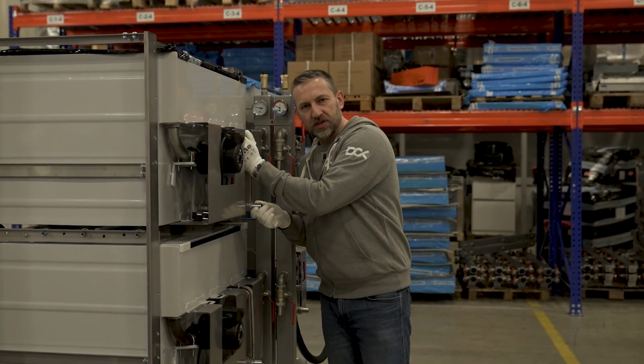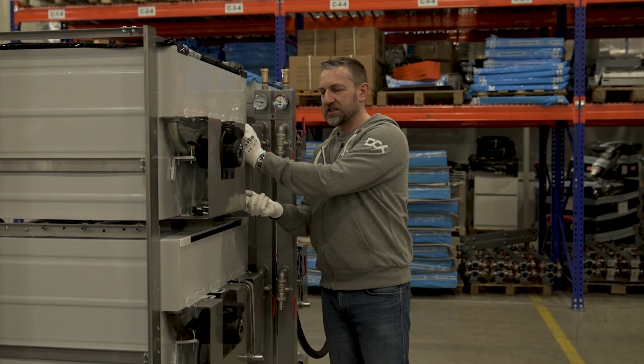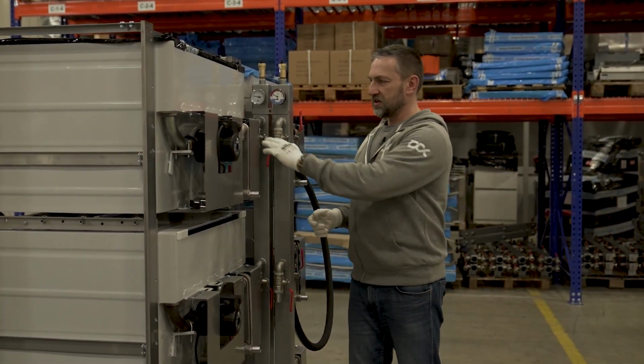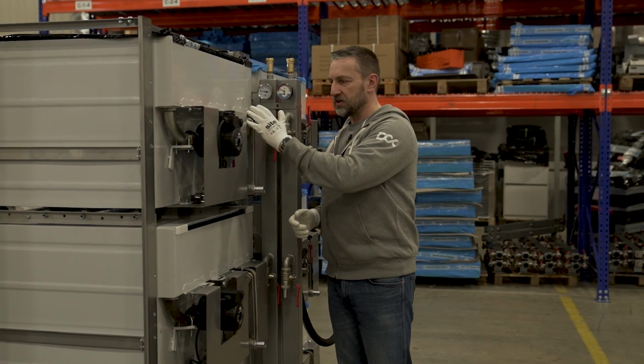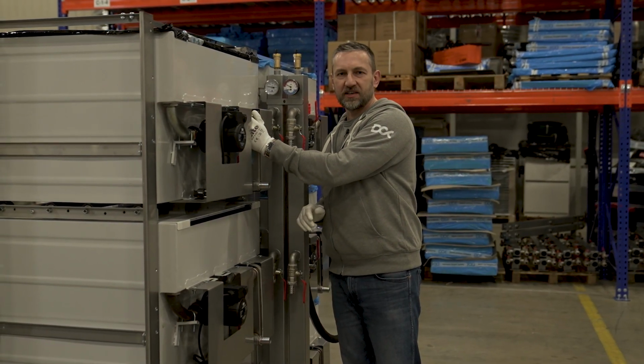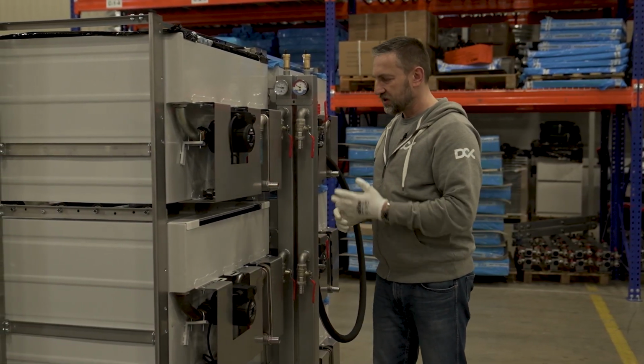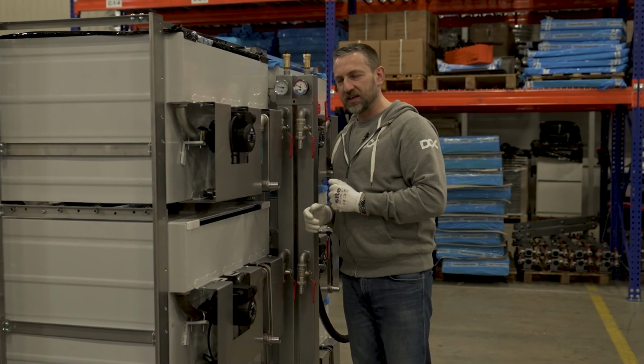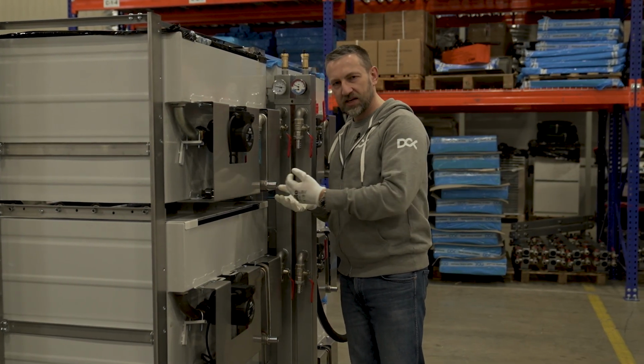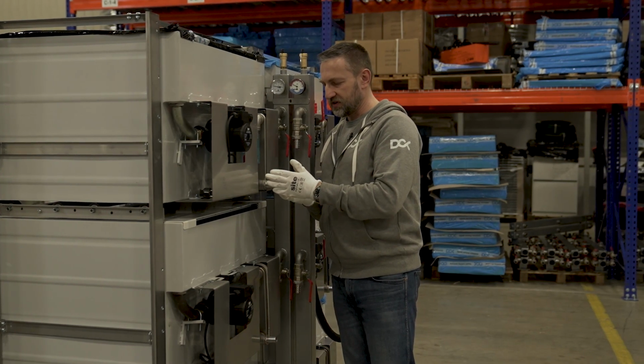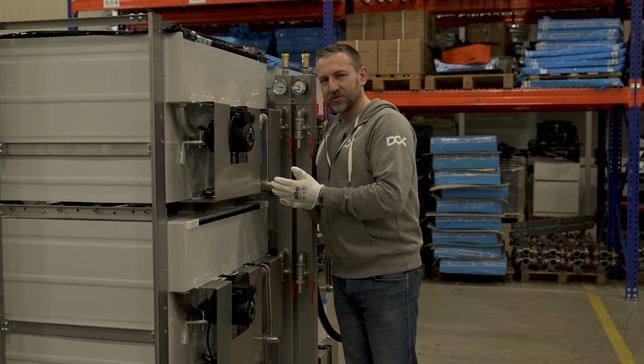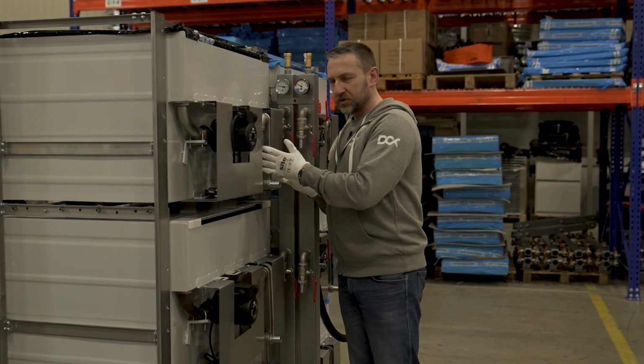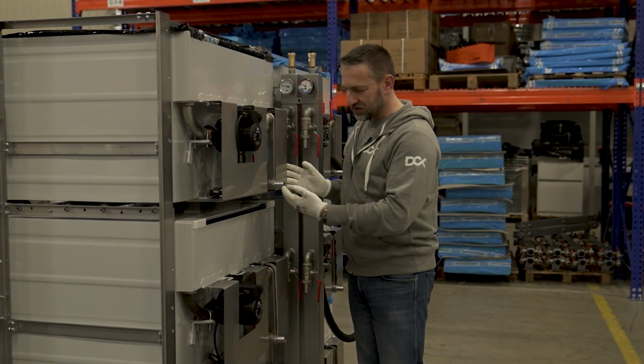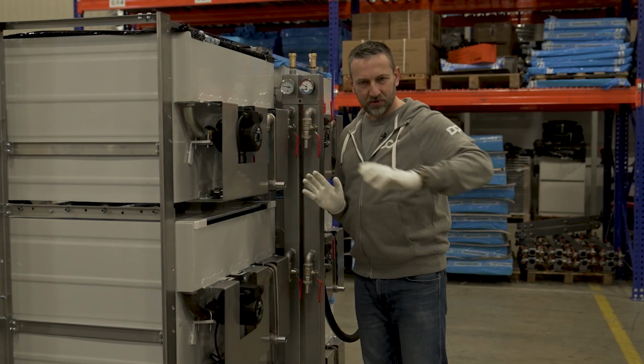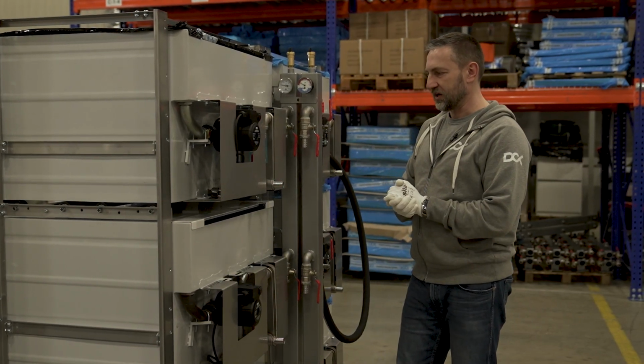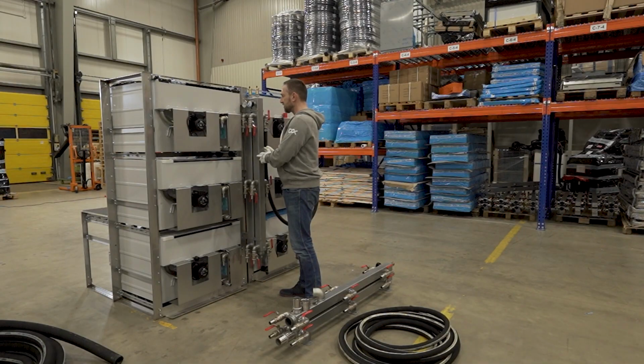On the primary loop side, here you have two fittings. One fitting is the outlet from the enclosure, so the hot or heated water goes out of the heat exchanger. Here is the inlet to the enclosure. At the bottom, you are sucking the colder, or let's say warm, water from the dry cooler system or facility loop to the heat exchanger, right? So it travels from the bottom to the top and from the top away from the enclosure. Simple as that.